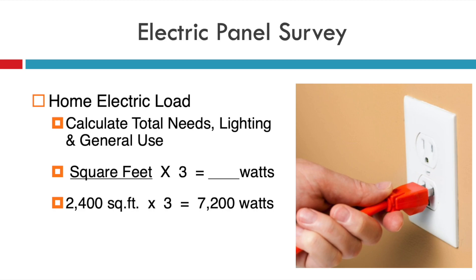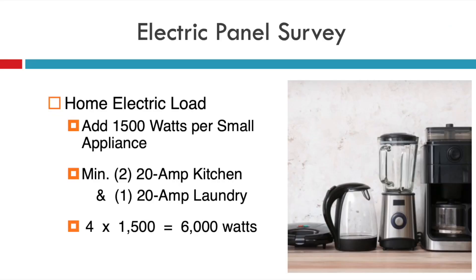That will give you the starting watts needed for just lighting and general use of the building. Then in step two, you have to look at the small appliance load. At minimum, as part of the National Electrical Code, you need to have two small appliance circuits in the kitchen and one small appliance circuit in the laundry room. So at minimum, three 20-amp circuits. Most homes have at least three, probably four or more, and I'm just going to use my house as an example.